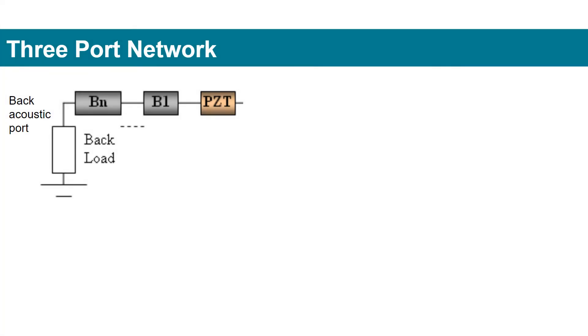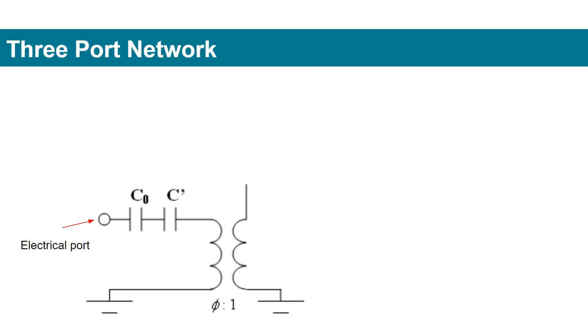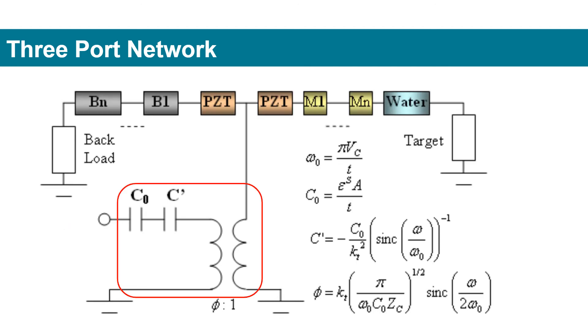An ultrasound transducer is represented by a three-port network with two acoustic ports connecting to the acoustic media in the back and the front of the transducer, and one electrical port connecting to the transceiver. One transformer and two capacitors are critical to the model.